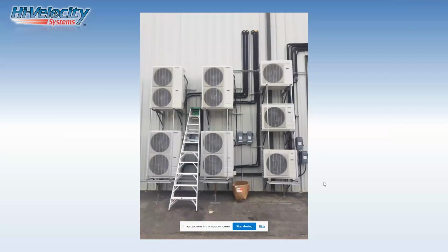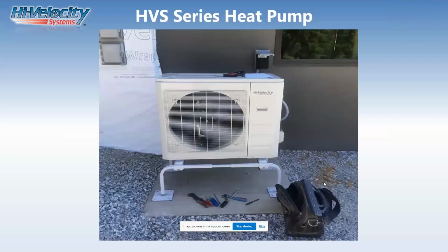Here's 29 tons of cooling heat pumps on the side of a building on a commercial project. These are heat pumps of ours that do both heating and cooling. Here's another picture of a heat pump. You see how it's raised off the ground? That is so important with a heat pump because it needs to go on defrost cycle and it will defrost and the water will drip. And if you didn't have it off the ground, it could freeze and build up ice and damage your unit.